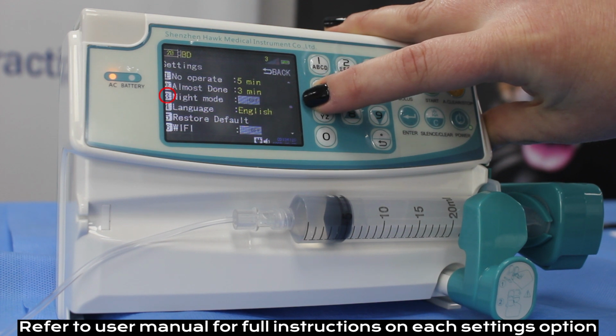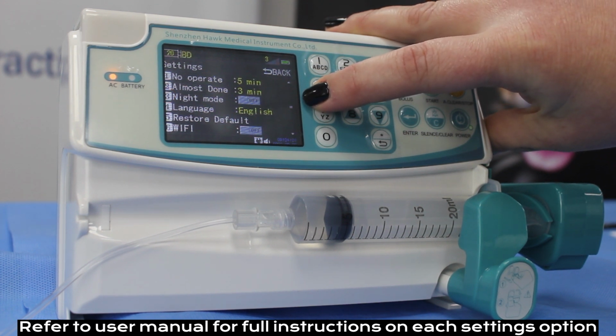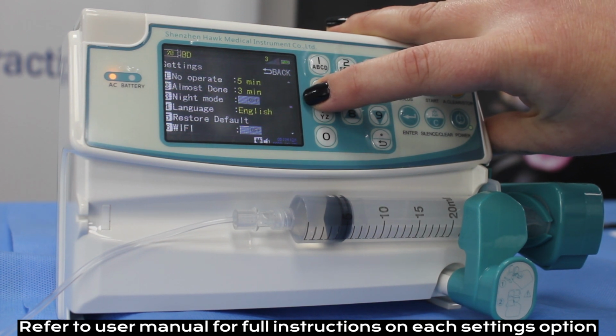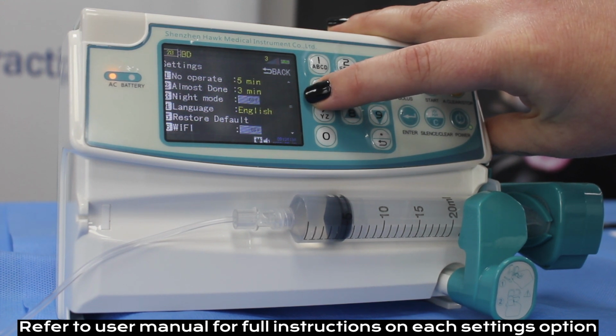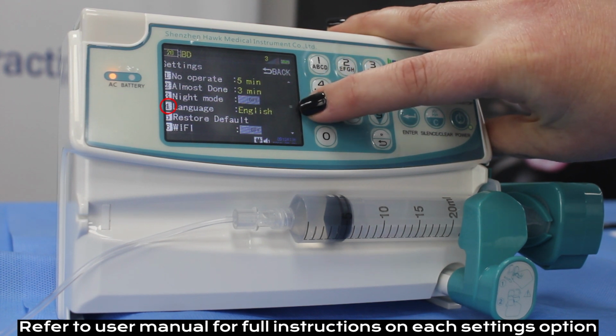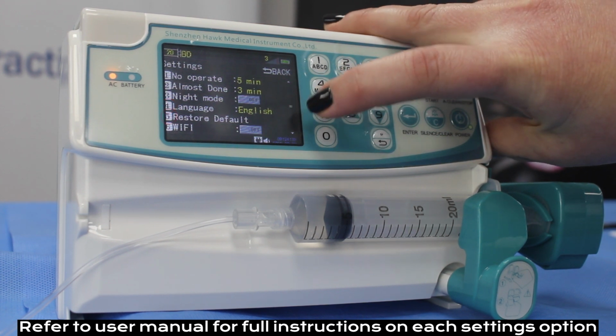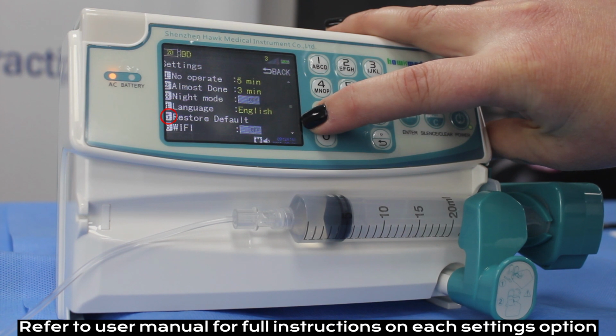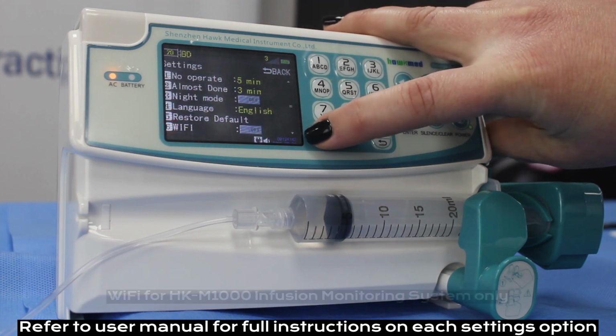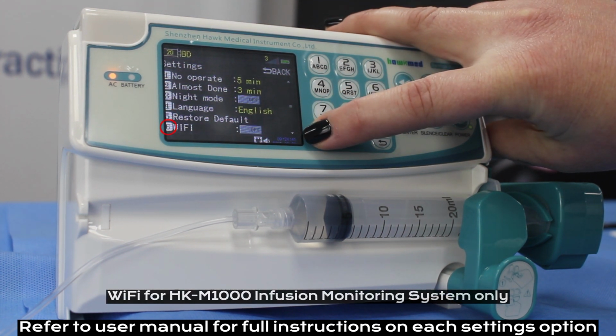Night mode, number 3, can be turned on if you're looking to use the pump in a lower stimulating environment or overnight. This mode removes the key beeps, dulls the light, and reduces the sounds emitted. 4 is your language settings. 5 can be used to restore to default factory settings. And 6 is for turning on and off your Wi-Fi.